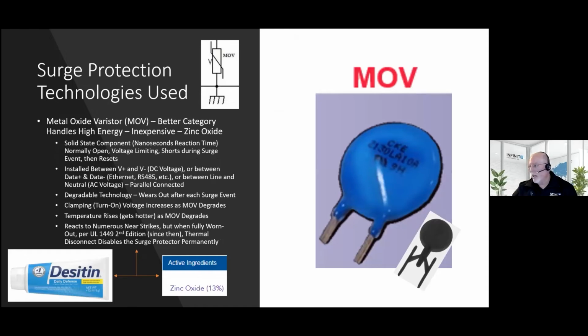So another technology is metal oxide varistors, which turns out to be zinc oxide, which is the same component used in diaper rash ointment. So I thought that was interesting. What they do is they bake it, and who knew it was an excellent surge protection device. So now this is also degradable, but it is solid state actually. And a colleague of mine gave a good example of this, of MOV. So consider it like a piece of paper. And after every time it's reacting to a surge event, you're poking holes in that piece of paper. Well, that piece of paper is your conduction material. And so as there's less material to conduct, the surge current still wants to get through it, but it's going through now a smaller and smaller pipe, which means that MOV technology gets hotter and hotter as it ages.